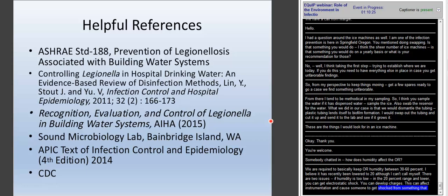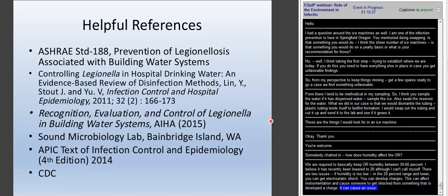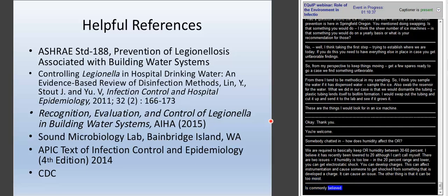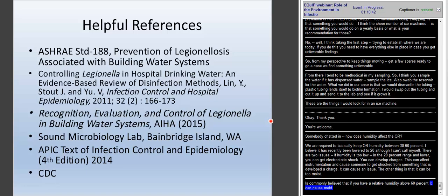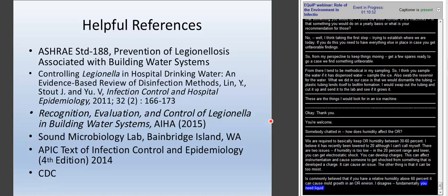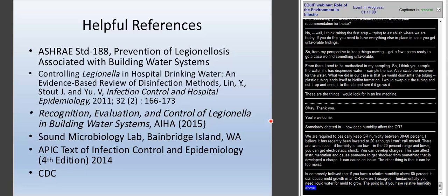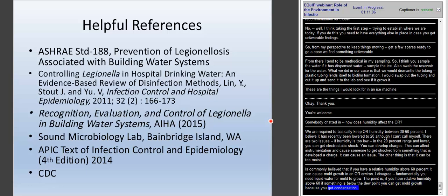The other issue is it can be too moist. It's commonly believed that if you have relative humidity above 60 percent, you can cause mold growth in an OR environment. I disagree with that, because fundamentally you need liquid water for mold to grow. But the point is, if the relative humidity is above 60 and the temperature of some piece of equipment or wallboard is below the dew point, you can get mold growth because you'll get condensation. So that's largely the issue with high humidity, covering both the low end and the high end.